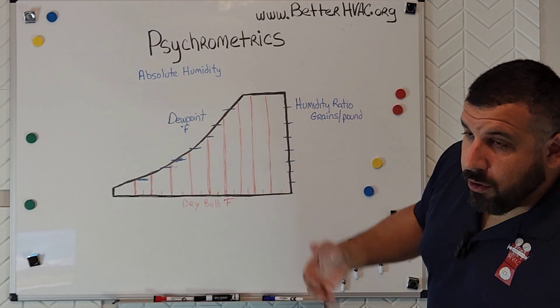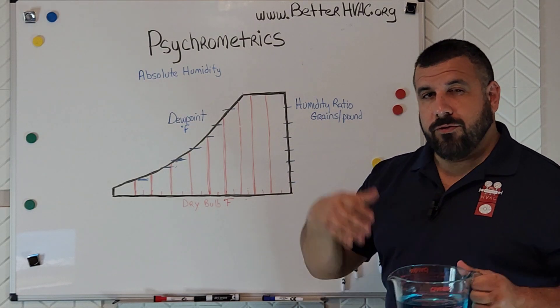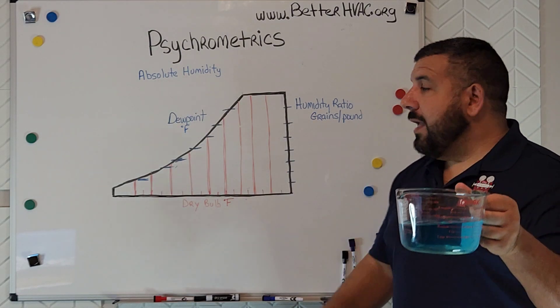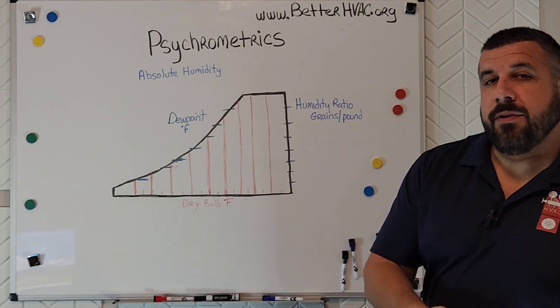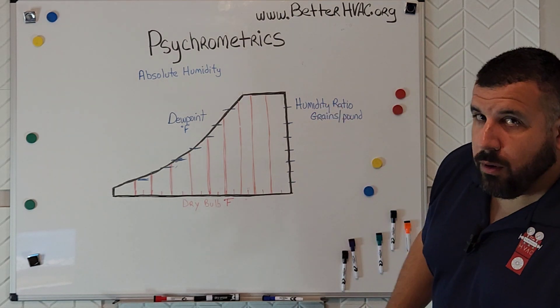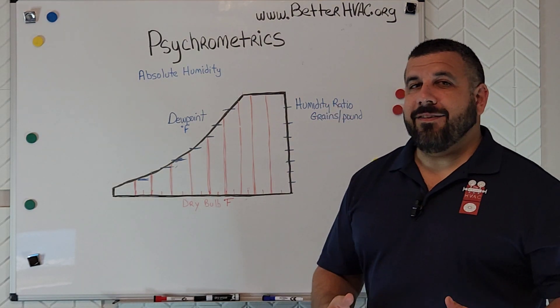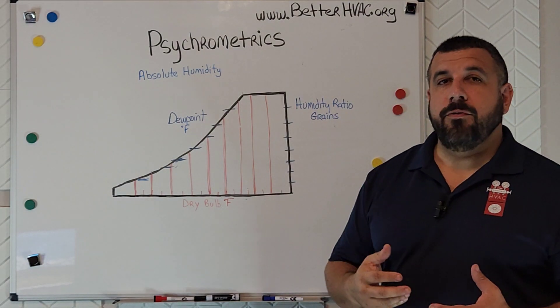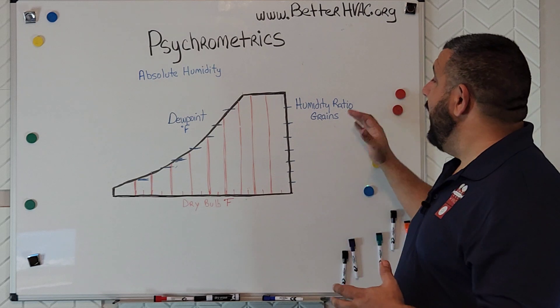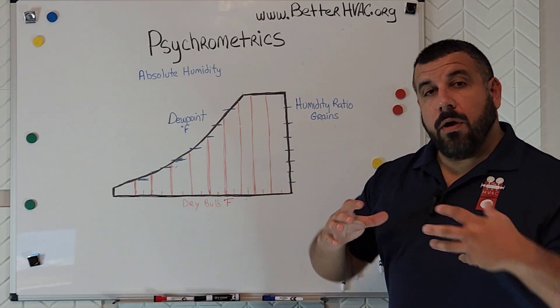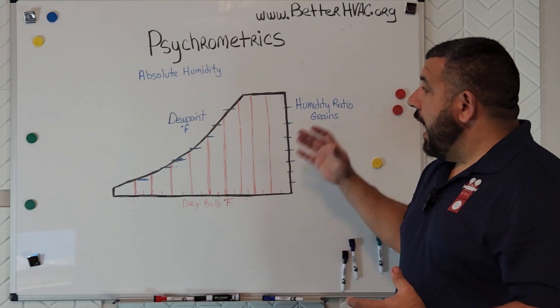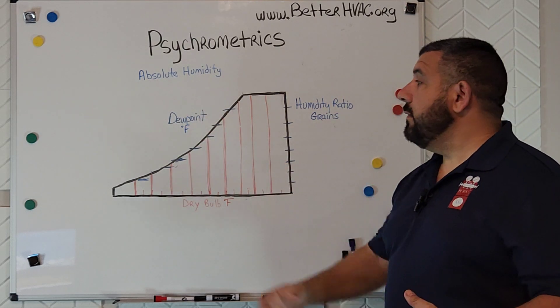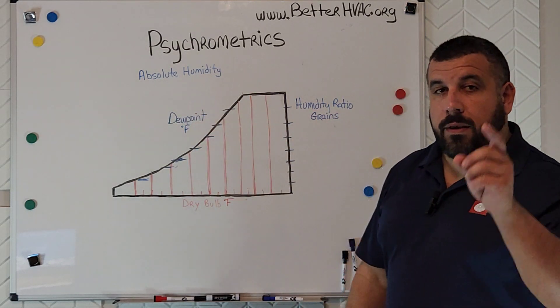Now, I've never heard of a grain of moisture — and just to put it in a little bit of context, this is a pint of water, and there are 7,000 grains in a pint of water. If that still doesn't make a lot of sense to you, you're not alone. There are only one or two formulas in psychrometrics where we really have to worry about grains. When we're talking about moisture in the air, I want you to be thinking about dew point — when you're thinking about how humid it is, think about it in terms of dew point.